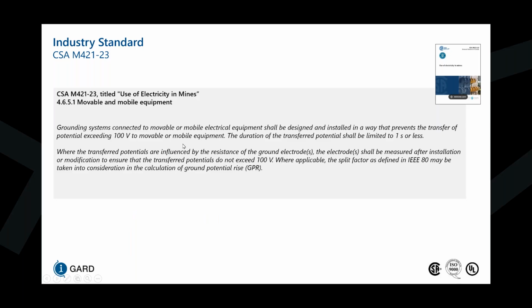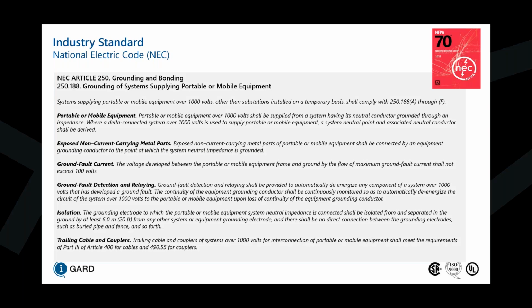When the transferred potentials are influenced by the resistance of the ground electrodes, the electrodes shall be measured after installation or modification to ensure that the transferred potentials do not exceed 100 volts between ground points. So they would just test the grounding electrodes to see what the difference in resistance is between the ground points and determine if there's a potential to be transferred that can exceed 100 volts. So you can use the split factor to take into consideration the calculation of ground potential rise. In the National Electrical Code, it says that systems supplying portable and mobile equipment over 1,000 volts shall comply with A through F. So for portable or mobile equipment over 1,000 volts, it shall be supplied from a system that is high resistance grounded or grounded through an impedance.